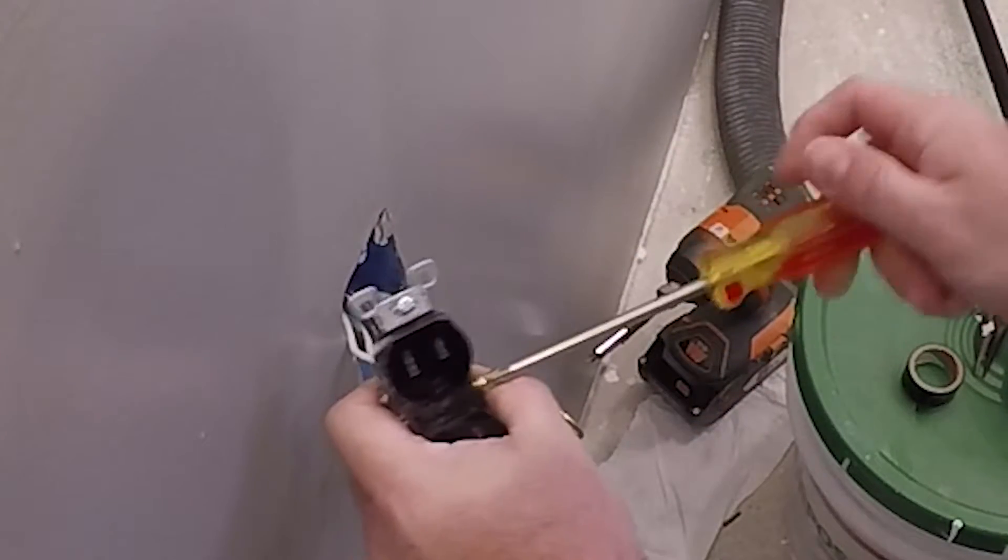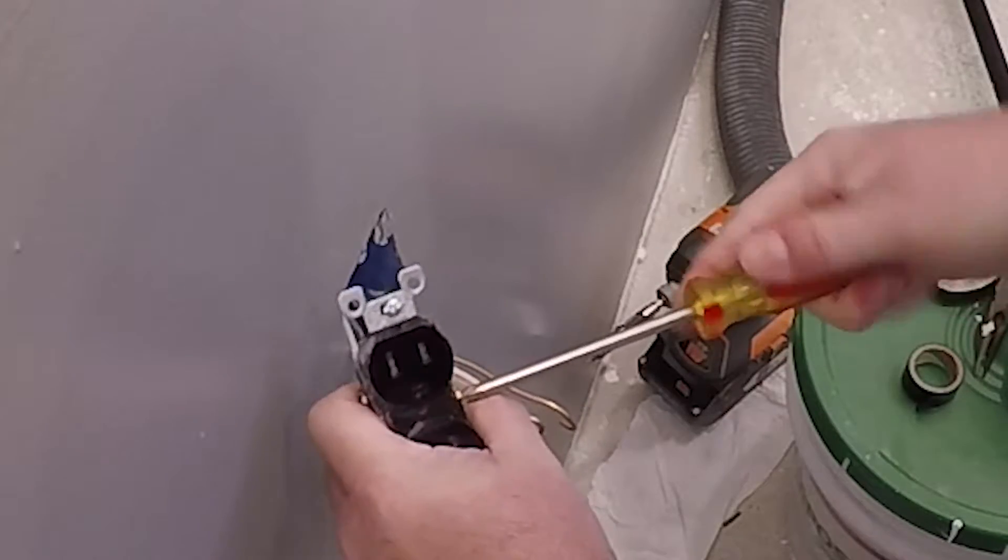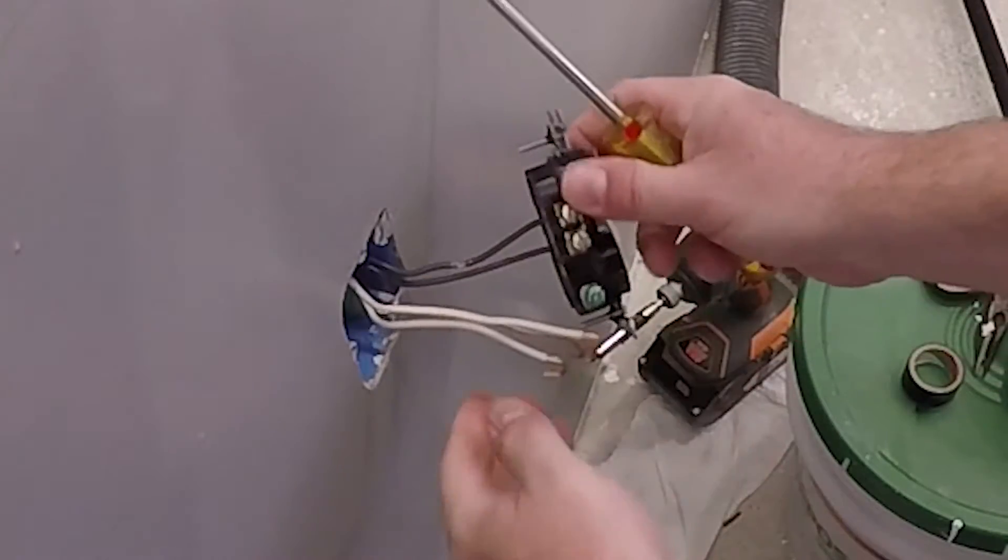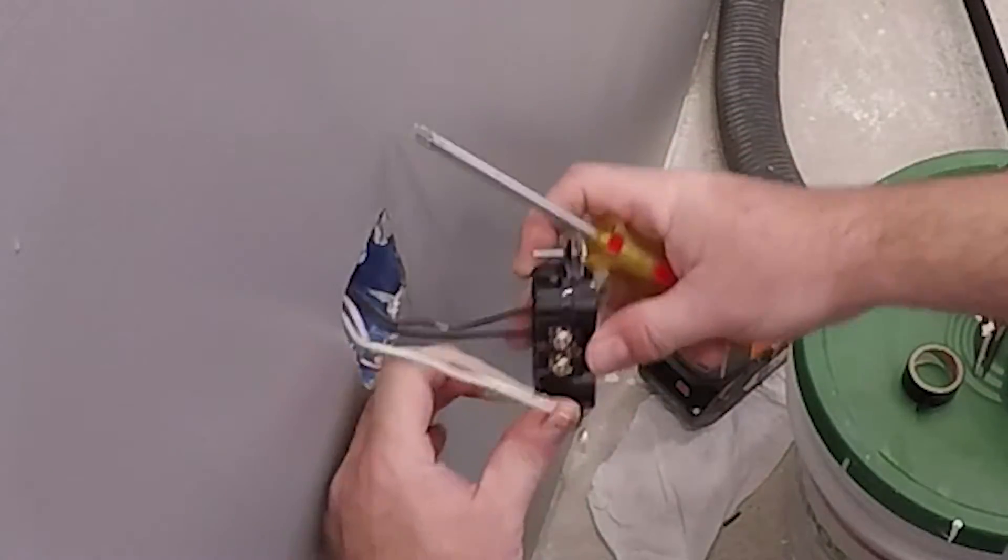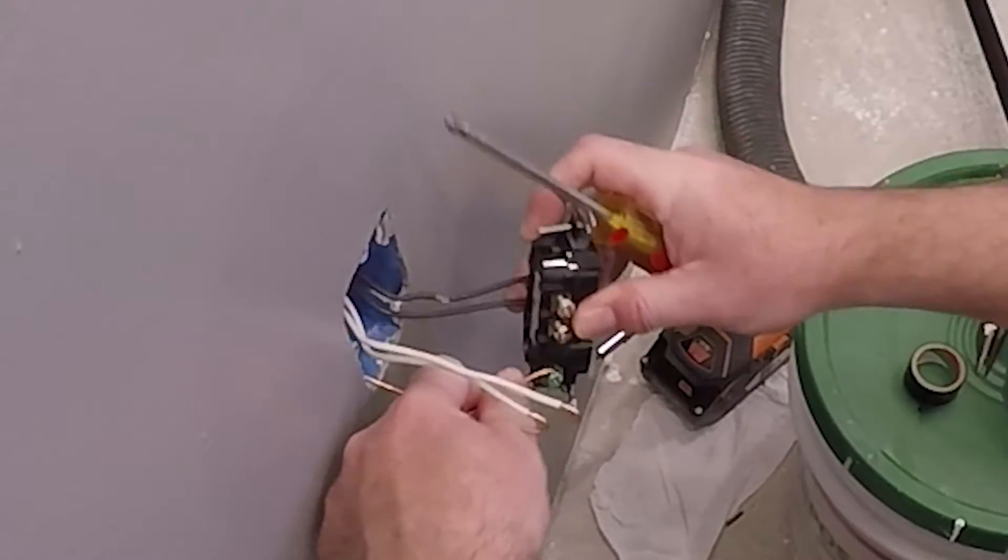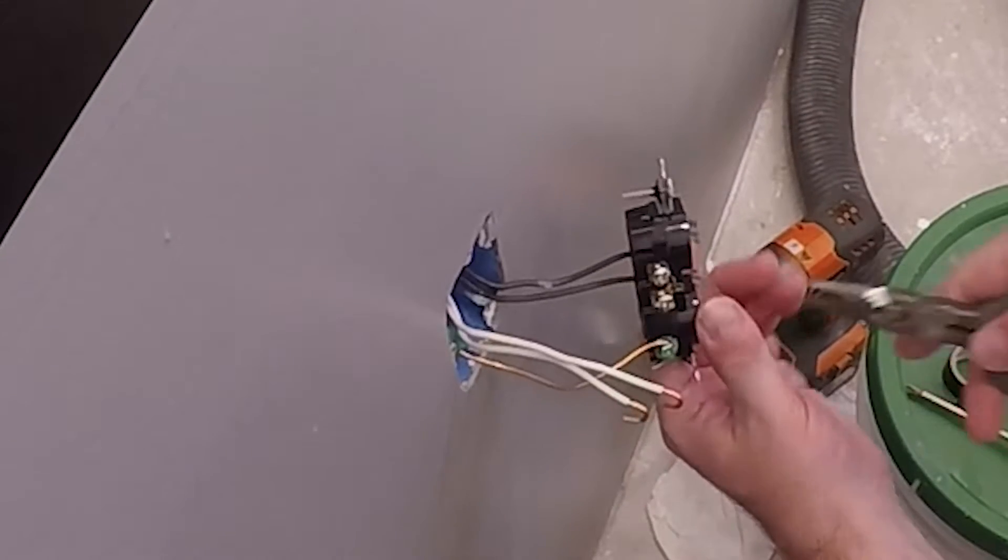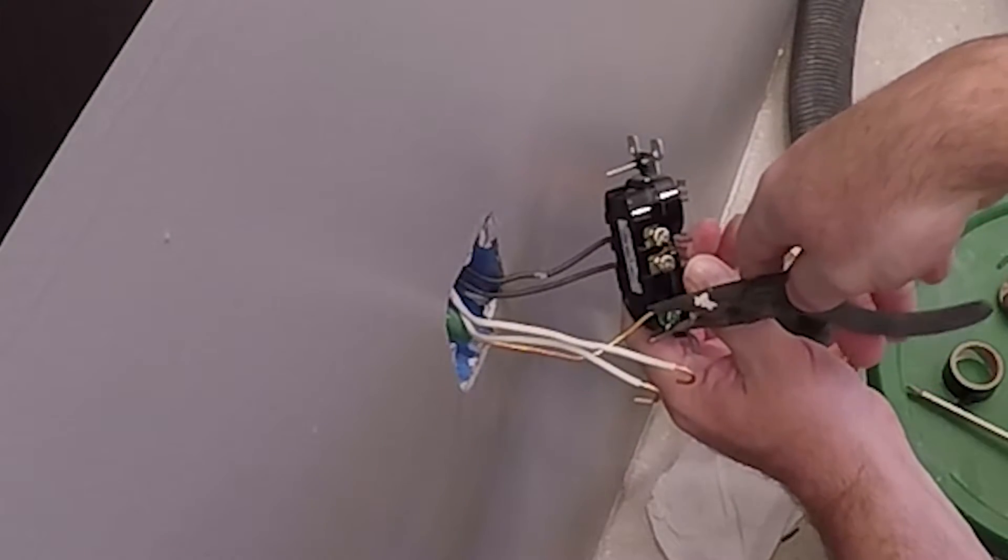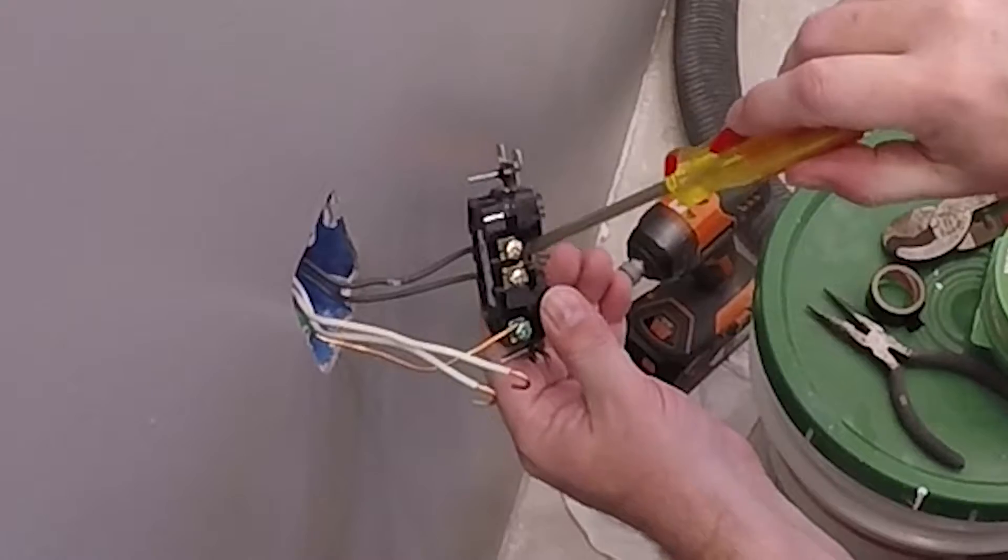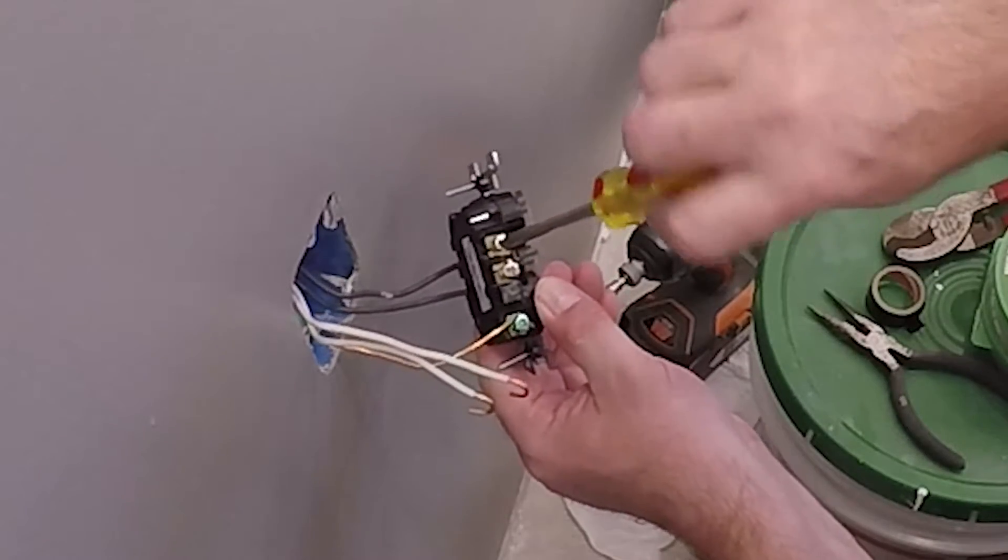Now, the hot gets connected to the smaller side, to the right side, to the brass colored screw. The hot is the black wire. White is the neutral, the bigger connector. Ground is the small middle connector. You see here I'm connecting the ground now. This is where I'm pinching the wire on the lug.